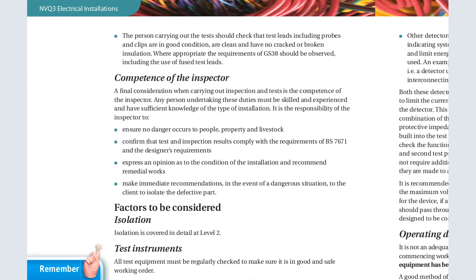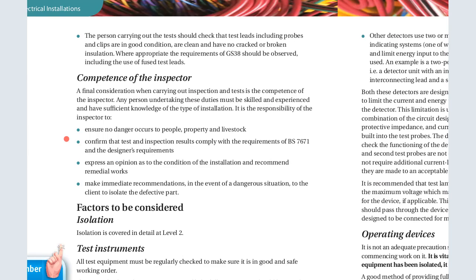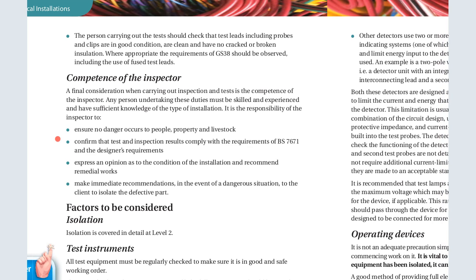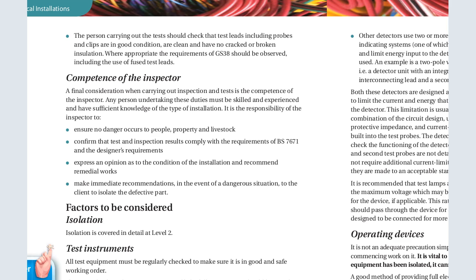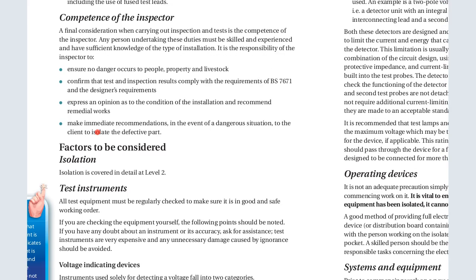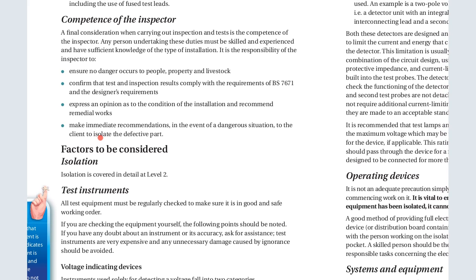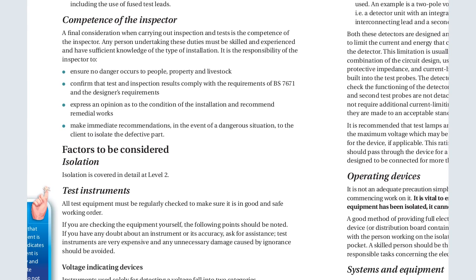Another one: we have to make sure that the person carrying out the test checks that the test leads, including probes and clips, are in good condition, clean, and have no cracks or broken insulation. Where appropriate, the requirements of GS38 should be observed, including the use of fused test leads. Competency of the inspector: the person doing the inspection also has to be competent, meaning a skilled person who is also experienced.